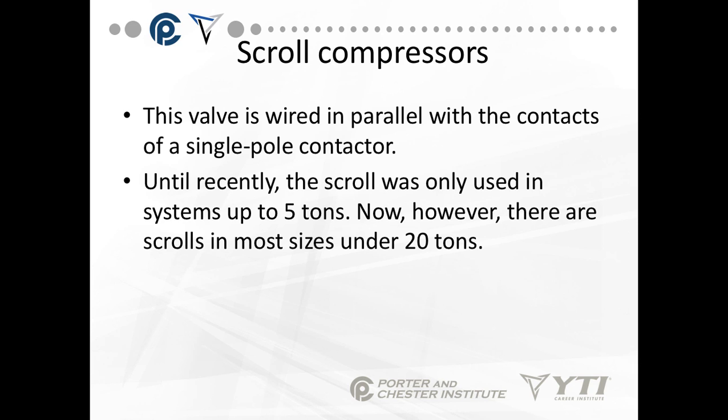The valve is wired in parallel with the contacts of a single-pole contactor. Until recently, the scroll was only used in systems up to five tons. Now we have scrolls in most sizes under 20 tons. Once you hit 20 tons, you get into some larger compressors.